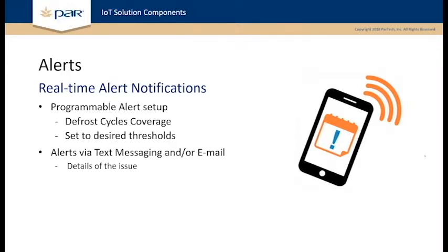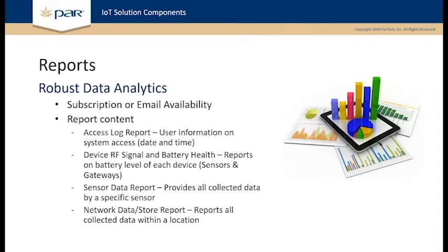An alert can be a text message, or it can be an email message, or it can be both if you desire. Alerts can also be set up to repeat, and you can set up the frequency you want it to repeat until the root cause issue is addressed. And in many systems, you can also set up an escalation to alternative staff if the problem isn't fixed in a specific amount of time.